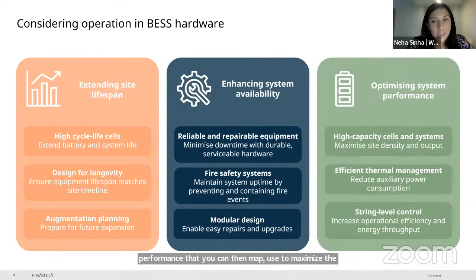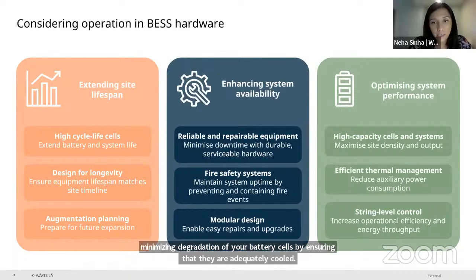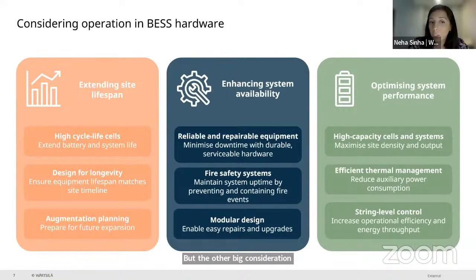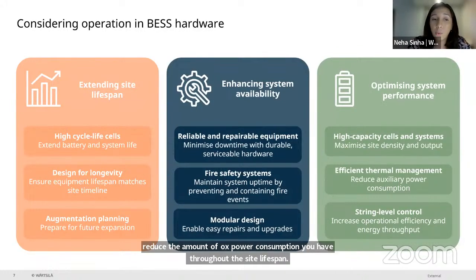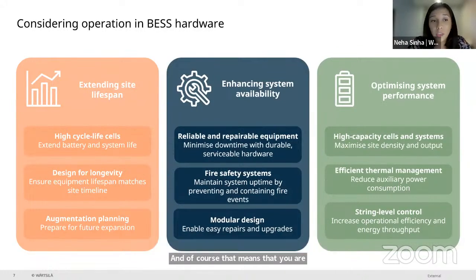Efficient thermal management is important for a few reasons. You want to make sure you are minimizing degradation of your battery cells by ensuring they are adequately cooled. But the other big consideration is that chillers tend to be the highest consumer of auxiliary power in your BESS system. So by making your chiller system more efficient, you can reduce the amount of aux power consumption throughout the site lifespan, which means you are maximizing the revenue you can gain from your site.